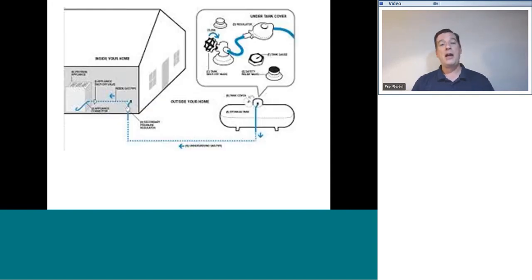Propane systems have a series of regulators involved, and where these regulators are and how they are set is going to be different in different applications, especially how far is that tank from the house and how big is the line going from the tank to the house. The smaller the line, the higher the pressure needs to be. The longer the line, the higher the pressure needs to be.